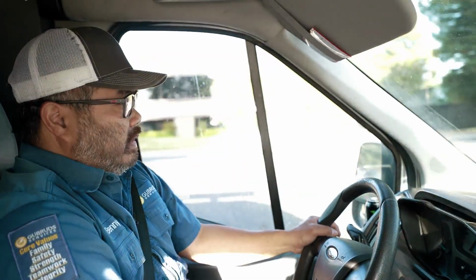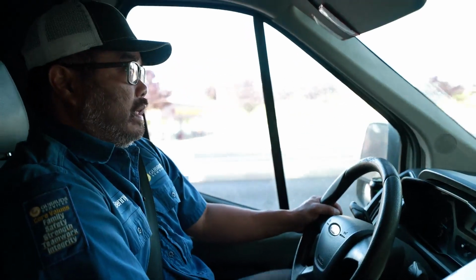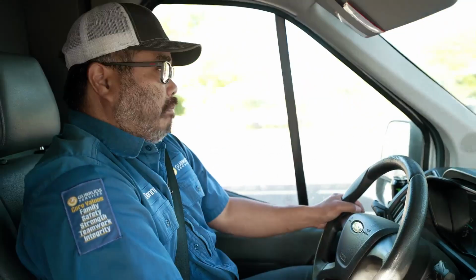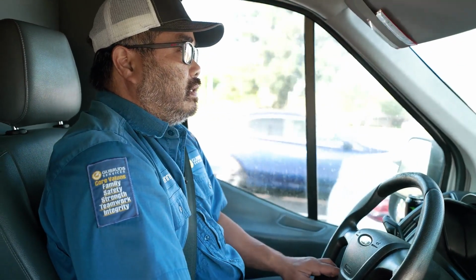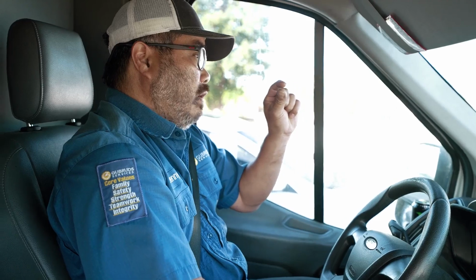I asked the customer, hey, did the other electricians show you this? Did they show you that your gutter, your grounding system, the wires, the connection points, everything in there was pretty much compromised by the water? And the morning sun hits that gutter box, so it's steaming up everything. Also, inside the Polaris connector, there was a clear Polaris connector, and inside it was also rusting, and I'll show you that later too.